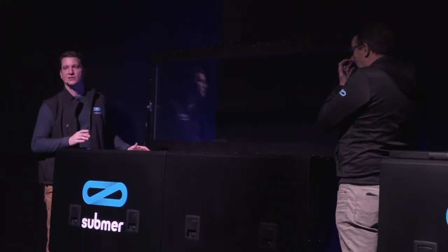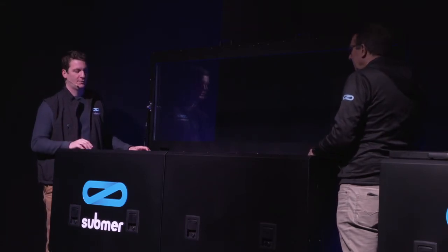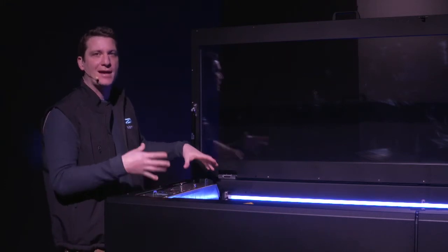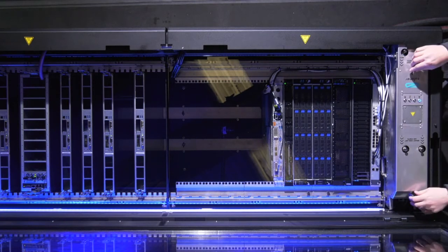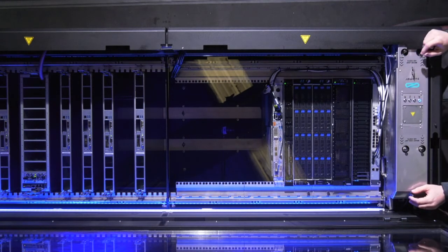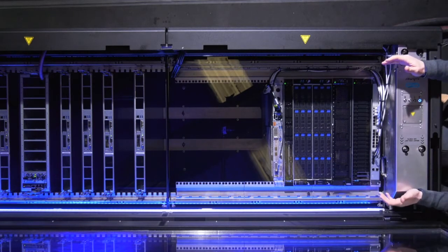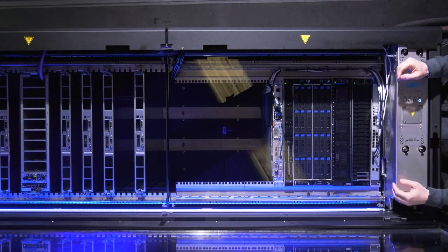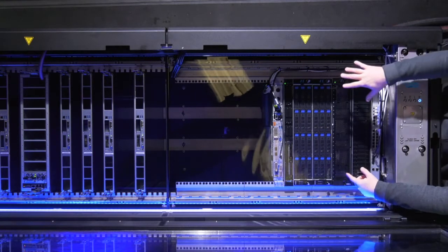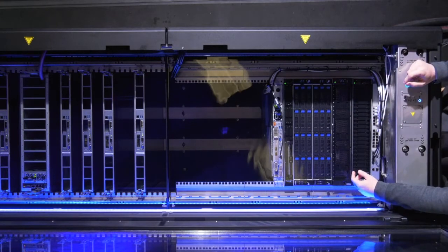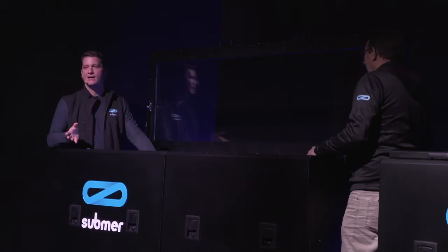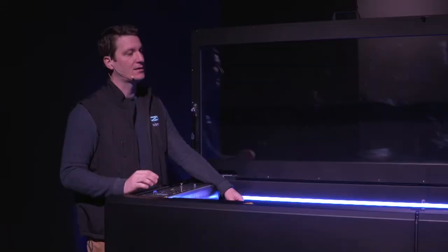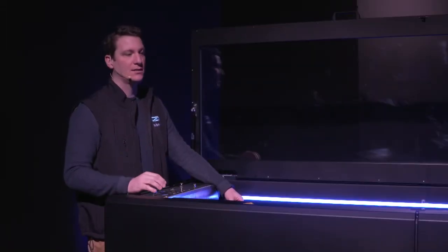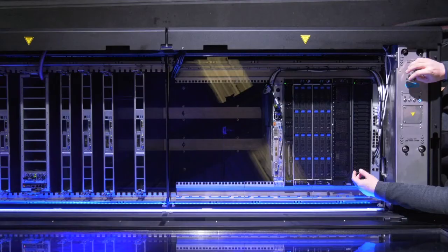The cooling distribution unit has certain redundancy built into it. It has 2 pumps. It is fully submerged, and it has a server form factor to be managed like a server and to be even extracted and replaced like a server, and we'll see very briefly how that is done. But what you can also see in this tank is that we have 2 types of hardware configurations: 19-inch equipment on this side of the tank, and 21-inch OCP equipment on the other side.